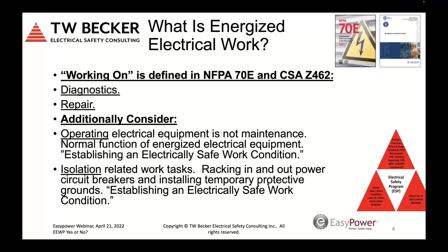So you need to take the list of energized electrical work tasks that are embedded in 70E and Z462, and you need to still interpret them and further classify what these work tasks are. So working on is diagnostics and repair, but operating is not working on, it's operating the equipment. And again, it's a function of the energized electrical equipment. It's designed to be operated. And with normal equipment conditions, I'm going to make a statement: you don't need arc flash or shock PPE to operate energized electrical equipment when you have a normal equipment condition. Now, that's an element of risk, which is a different discussion than the need for the permit.